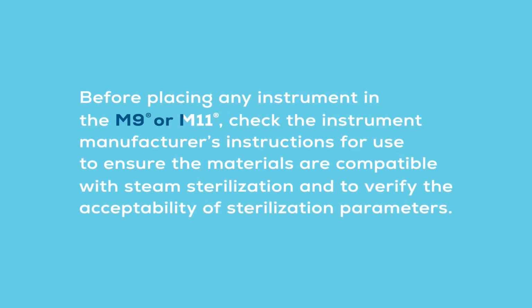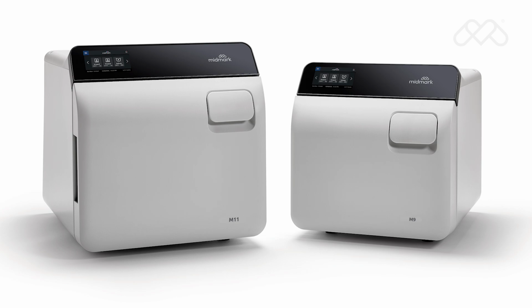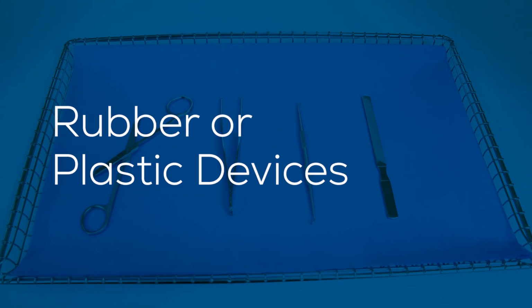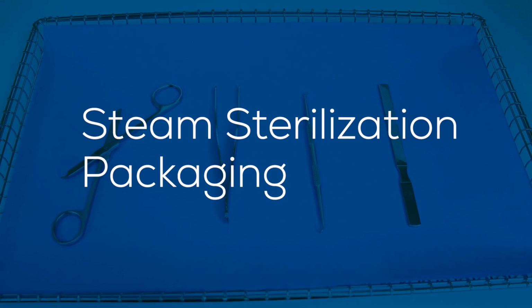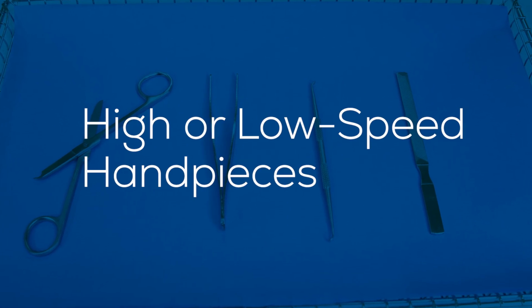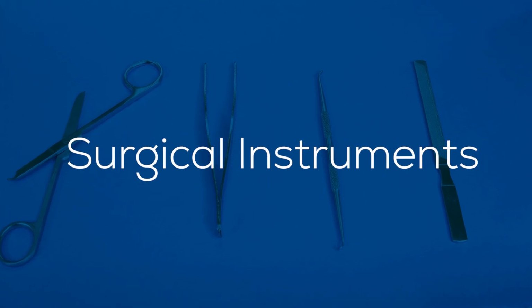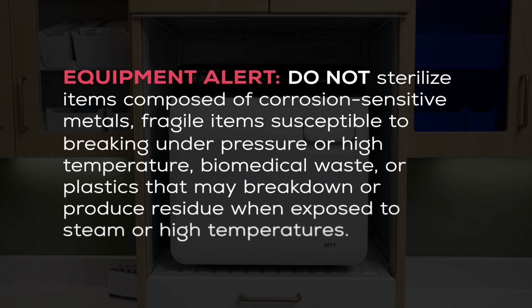Before placing any instrument in the M9 or M11, check the instrument manufacturer's instructions for use to ensure the materials are compatible with steam sterilization and to verify the acceptability of sterilization parameters. Midmark steam sterilizers are designed to sterilize metal instruments, rubber or plastic devices, steam sterilization packaging for medical devices, cassettes, high or low-speed handpieces, and surgical instruments. Do not sterilize items composed of corrosion-sensitive metals, fragile items susceptible to breaking under pressure or high temperature, biomedical waste, or plastics that may break down or produce residue when exposed to steam or high temperatures.